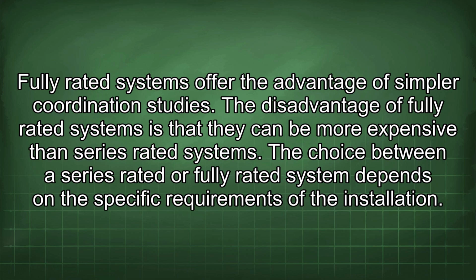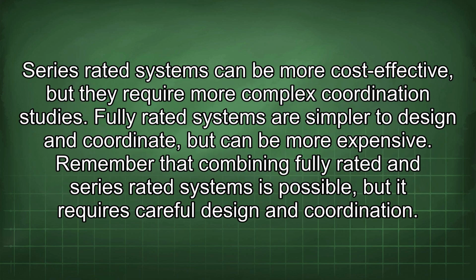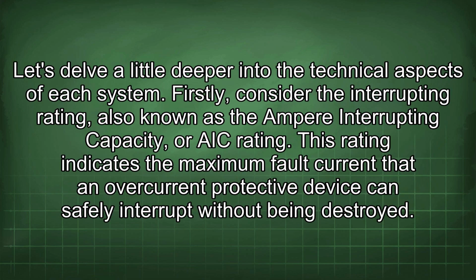The choice between a series-rated or fully rated system depends on the specific requirements of the installation. Series-rated systems can be more cost-effective, but they require more complex coordination studies. Fully rated systems are simpler to design and coordinate, but can be more expensive. We remember that combining fully rated and series-rated systems is possible, but it requires careful design and coordination. Let's delve a little deeper into the technical aspects of each system.